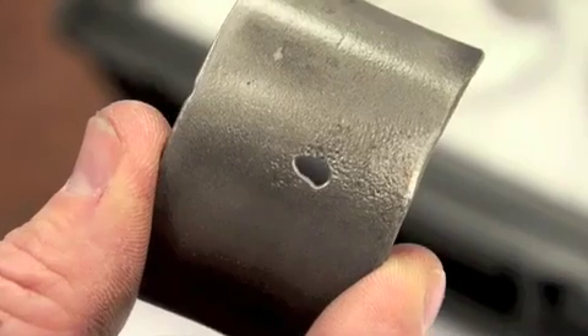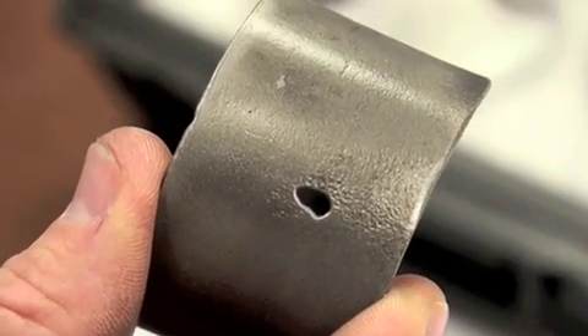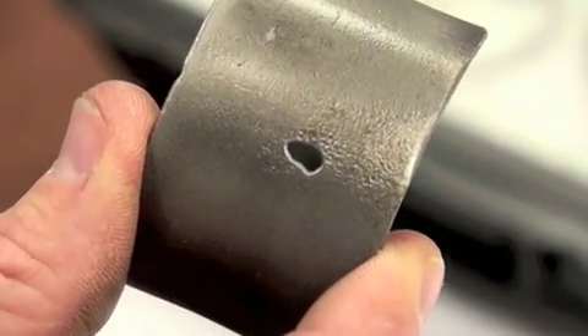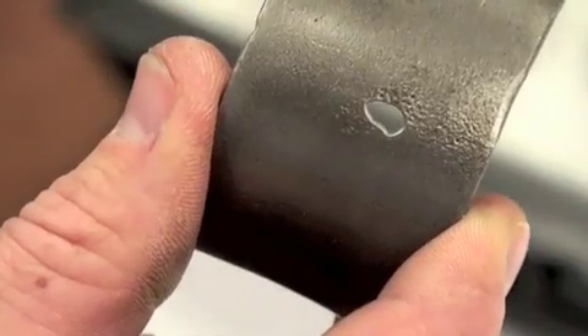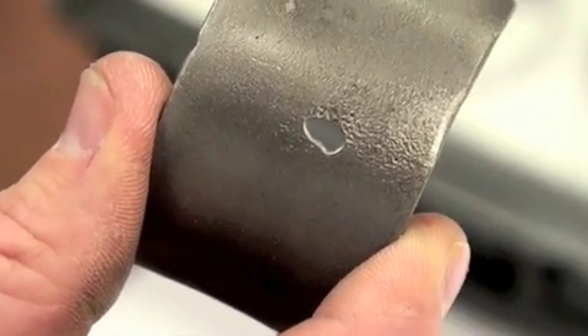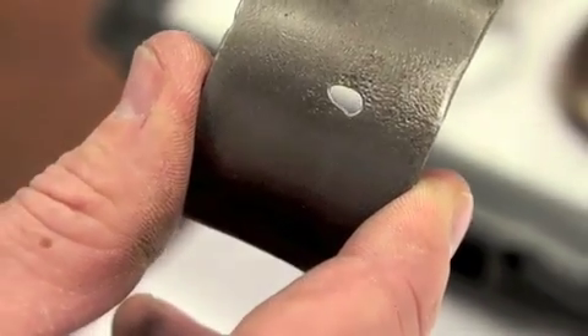Pinhole leaks are often caused by microbiological activity. Some of the other signs you should be looking for: air compressor running often, system tripping, false alarms, and foul smell when the system is drained.